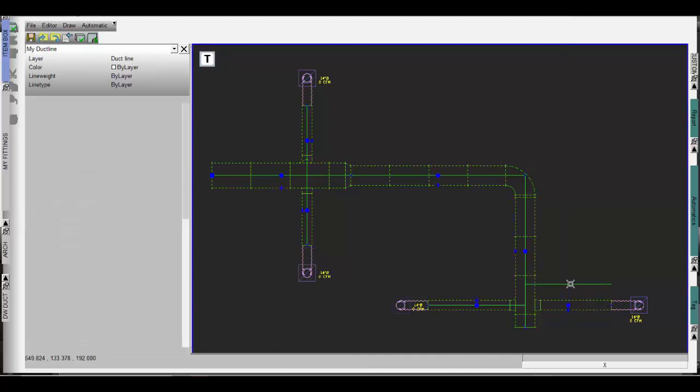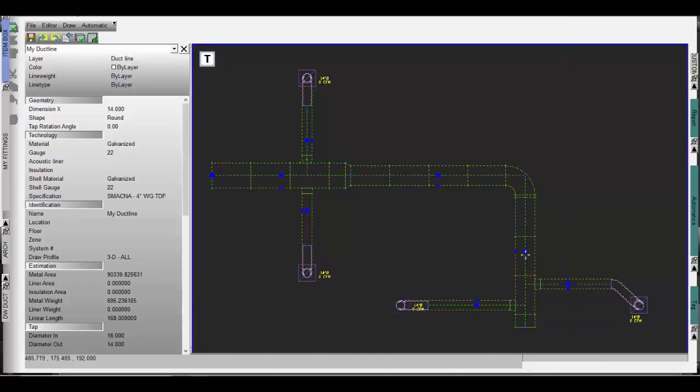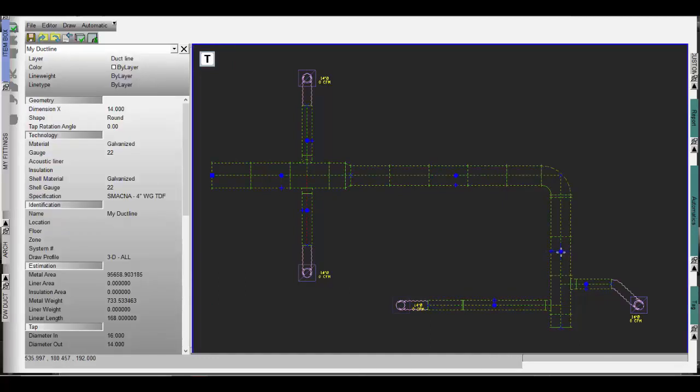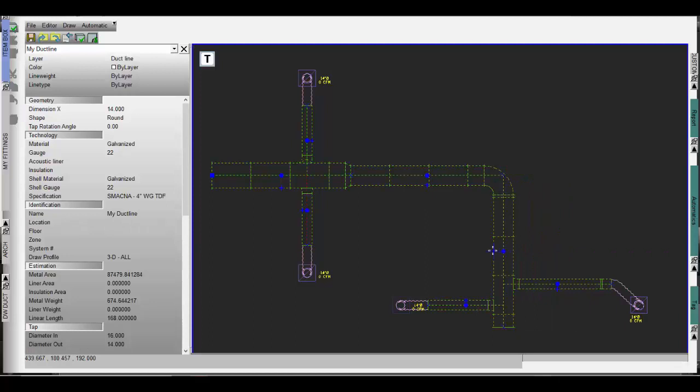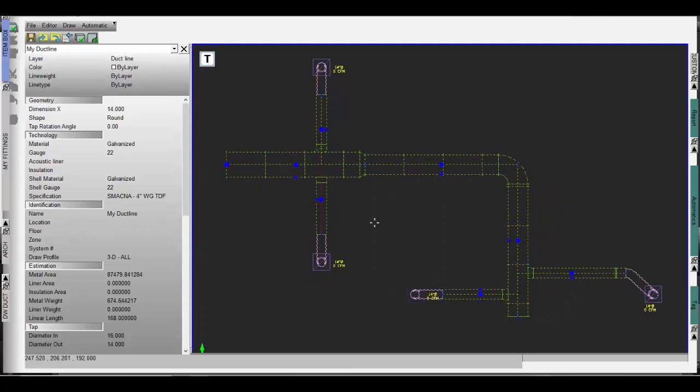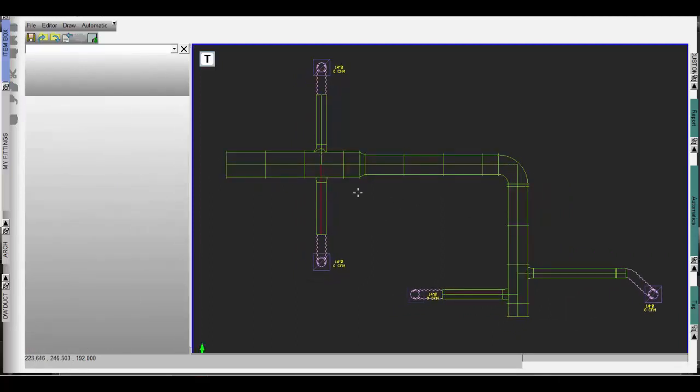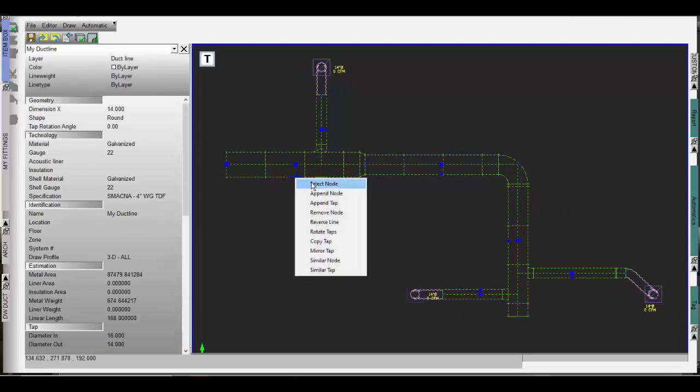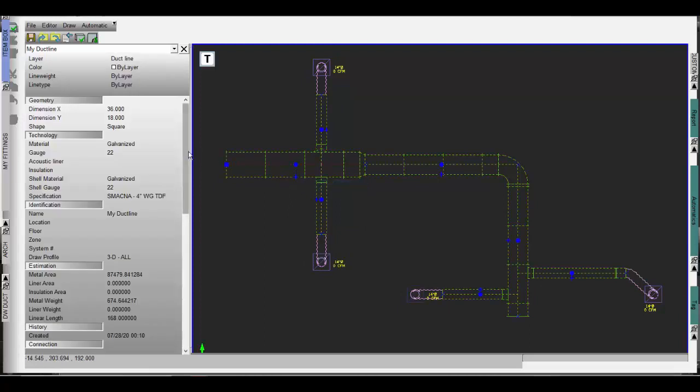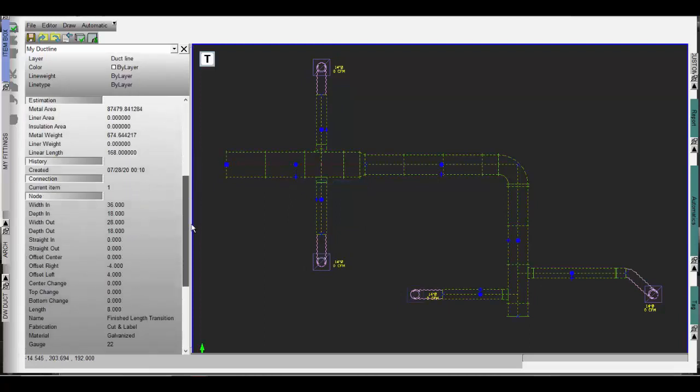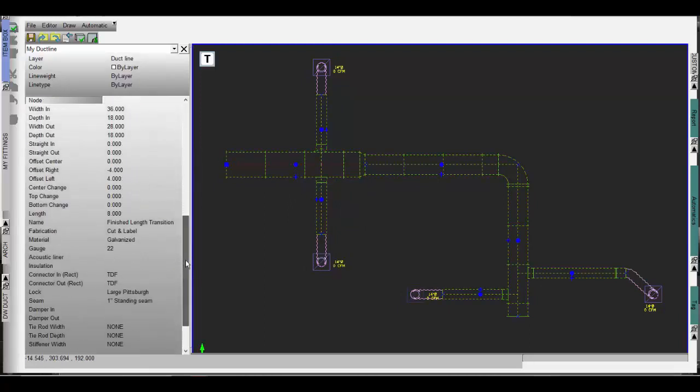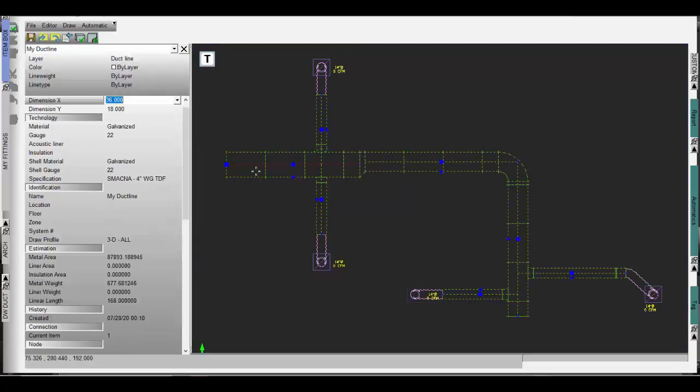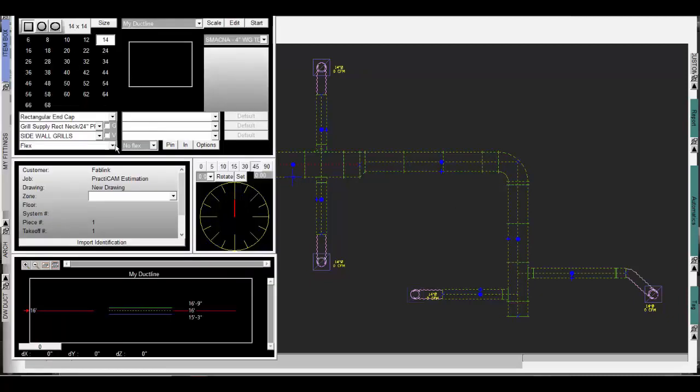Stretching commands were added to simply move branches and main lines wherever we want just by dragging the duct line nodes. And note, upon every single move, the duct line is re-optimizing the line based on the preferences of min-max straights and stock sizes so you don't have to erase or redraw anything. Here we will adjust the transitions properties in the middle of the run, direct from the property box. Just pick the parameter you want to change, press enter, and notice the way duct line edits everything to accommodate us.